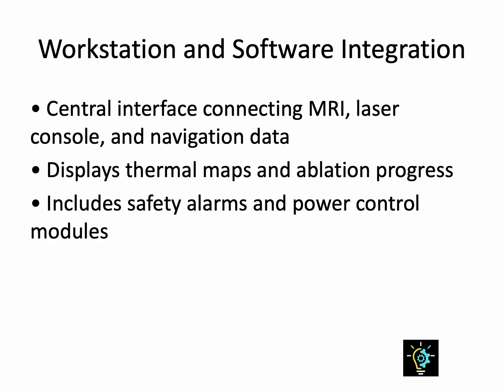The workstation functions as the operational core of LiTT. It consolidates all data streams, MRI images, temperature readings, and laser parameters, into a unified interface. Engineers develop intuitive GUIs to visualize ablation zones and control laser emission profiles. Built-in algorithms calculate estimated tissue damage zones, while safety systems issue alerts when thresholds are exceeded. The software architecture must ensure low latency data exchange between MRI and laser console. Any lag or desynchronization could compromise safety. Integration testing, redundancy protocols, and cybersecurity features are key components of the system's reliability.